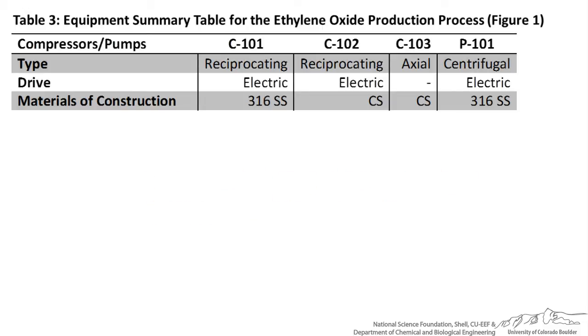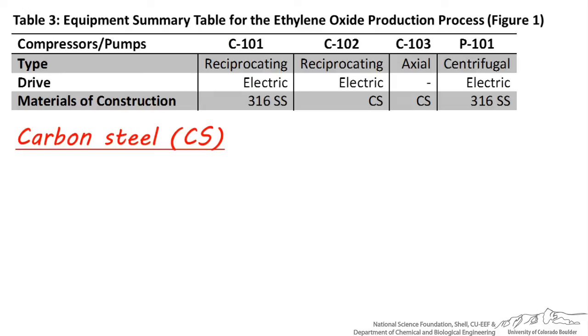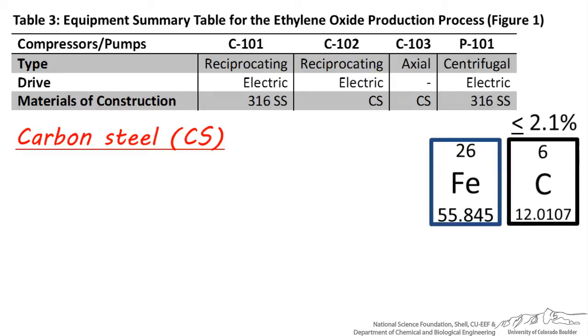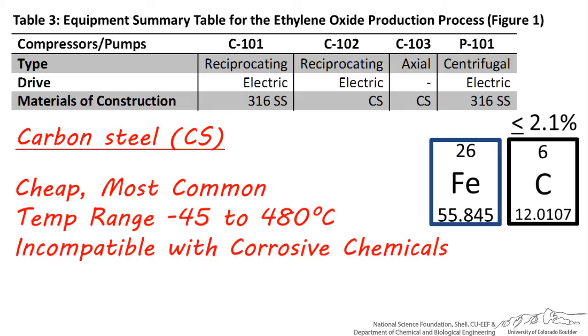Of all materials used in chemical process units, the most ubiquitous is carbon steel, abbreviated CS. Carbon steel, like all steels, is mostly iron, and it features up to 2.1% carbon, which is added for hardness. Carbon steel is probably the most widely used material in chemical processes because it's cheap and can withstand fairly high and low temperatures, so long as the process fluid is not corrosive or reactive.